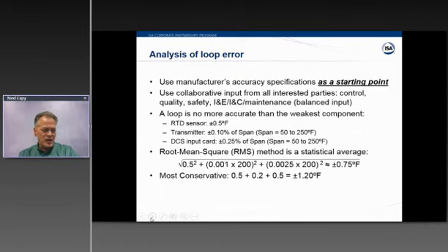When you look at a loop test, there are some considerations that you need to apply when it comes to what the total loop error is. So here's an example where you have an RTD sensor, transmitter, and the DCS input card. All three elements can drift, can change, and have a measurement accuracy. So the RTD sensor, in our example, maybe it's within half a degree. The transmitters are pretty good today, and with a span of 50 to 250 as an example, you could say that's 0.1% or 0.2 degrees. The DCS input card might be slightly higher, might be the same. But if you look at these three numbers, the weakest element in the loop would be the sensor, the half a degree error. So how do you analyze the accuracy of the loop?